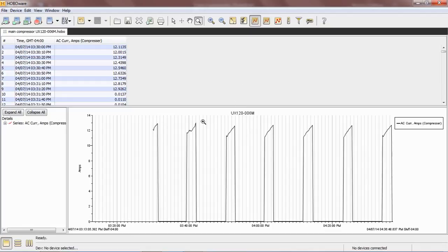because you could put a clamp-on meter on this load when it's running to figure out what the energy consumption or power consumption is, depending on what you're interested in. Most of the applications I've seen, people are looking for power, and then they calculate energy from that. But either way, you could put your clamp on there when it's running to figure out what it's drawing, and then just figure out the runtime. Let me show you how you would do that using one of our runtime loggers.